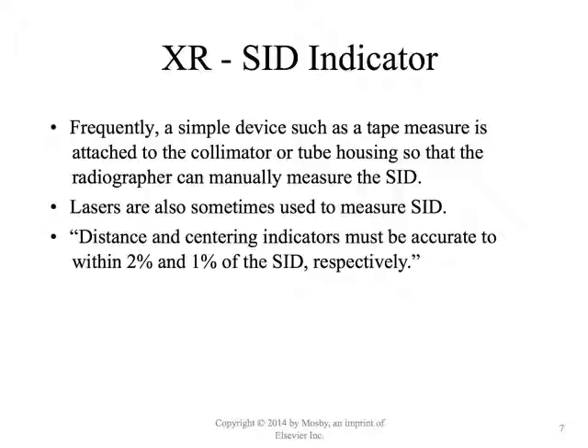The distance and centering indicators must be accurate to within 2% and 1% of the SID respectively. So the distance must be within 2% and the centering indicators must be within 1% of whatever that SID is. Typically, the way they do this for X-rays, the SID measurement, is they put the SID at like 100 centimeters, right? And then they make a measurement to see if the distance indicator is working correctly at that 100 centimeter distance, right? Why do they use 100 centimeters? Because it's that much easier to calculate 2% from 100, right?